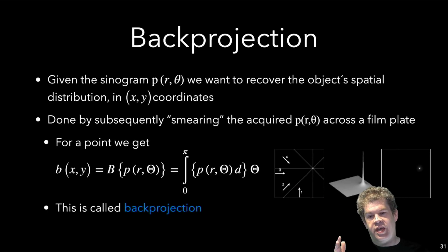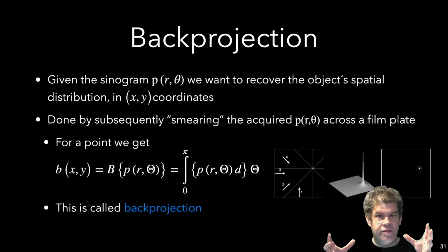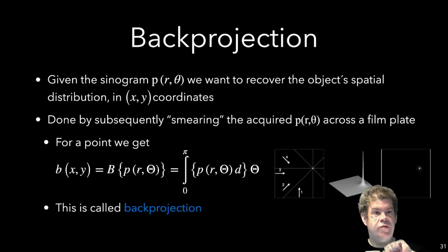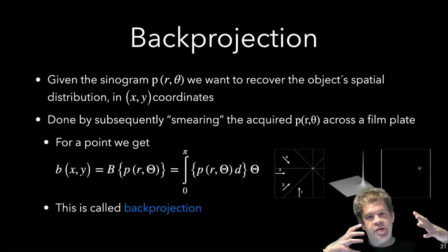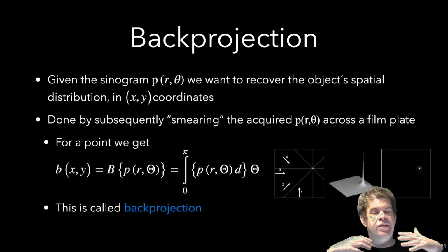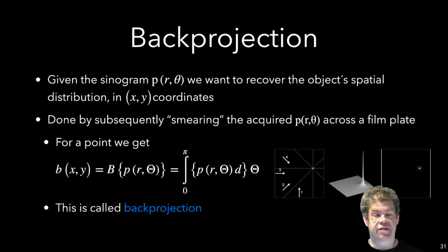This back projection is taking the sinogram and turning it into the actual data that created the sinogram, kind of solving the inverse problem: which superposition of sines led to this image? There are a ton of ways, but two obvious ways to solve this. One is to literally throw all of those measurements that I did into a system of equations and solve it. You can do that, that is perfectly fine. And as a matter of fact, with increasing computational power, this is more and more often used in actual scanning devices.